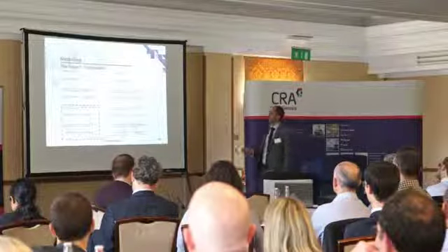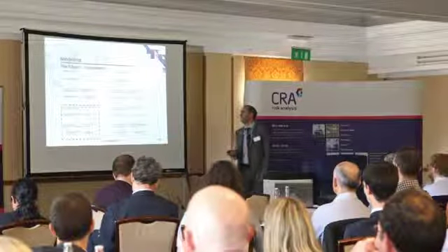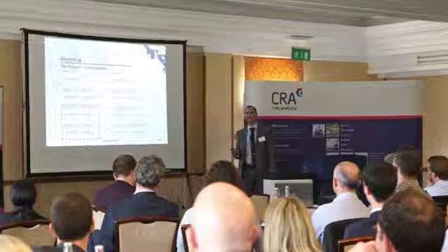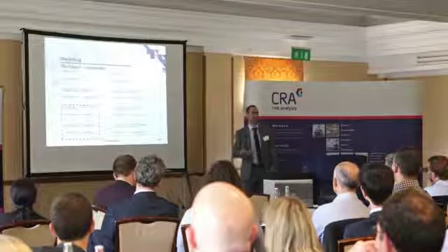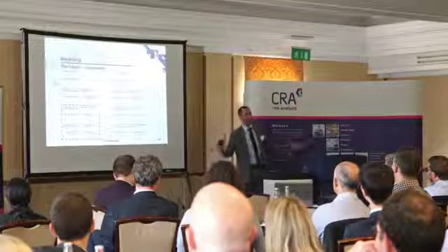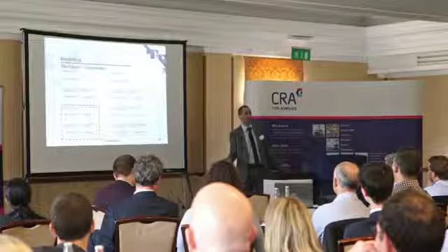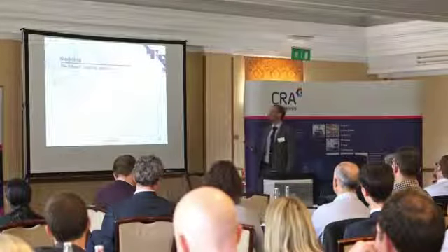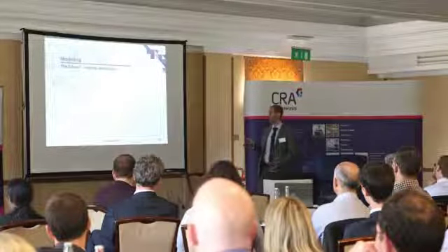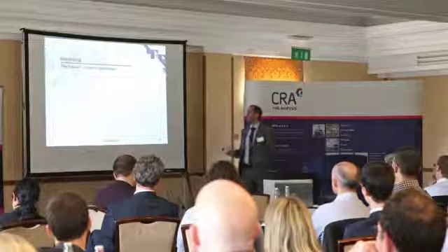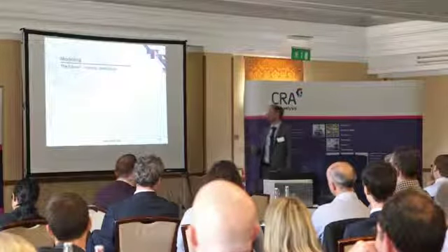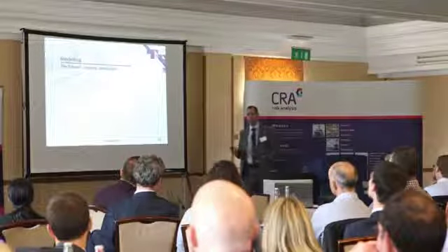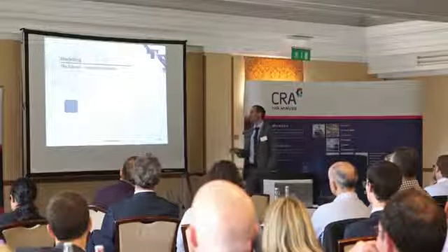Now there is a problem with this approach, and especially for traditional modellers in the crowd, I'm pretty certain you'll spot what the problem is. Traditionally the modelling looks at a seismic event across the whole site, and you lose everything at the same time, no matter how many systems, because we're all seeing the same acceleration. That is called seismic correlation. It's something that is being looked at a lot more in depth, and it strikes at the heart of whether you're being very conservative or whether you want to be best estimate. So let's look into this a bit more.